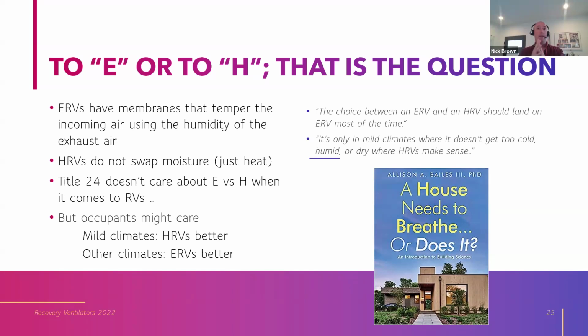So that means that some of the humidity in the outgoing air goes into the incoming fresh air, but only in an ERV. And I would ask you to consider, is that always a good thing? Is it sometimes a good thing? Is it never a good thing? These are nuanced questions, which is why this ERV, HRV debate is so common on message boards. It's something with pros and cons and no simple answer.